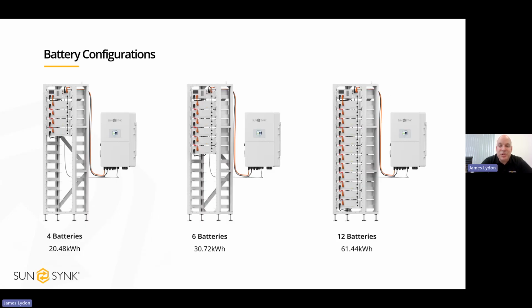Battery configurations. With all the high voltage hybrid inverters, the minimum number of batteries connected to each one is 4. This shows different configurations: we've got 4, 6, and 12. The minimum required for the battery startup voltage range is 4. In the picture on the left, you've got the four batteries, and at the top, you've got the battery management unit. The batteries connect in series up to that battery management unit at the top, and that then connects to the inverter.